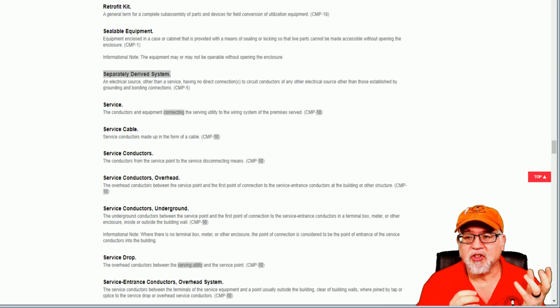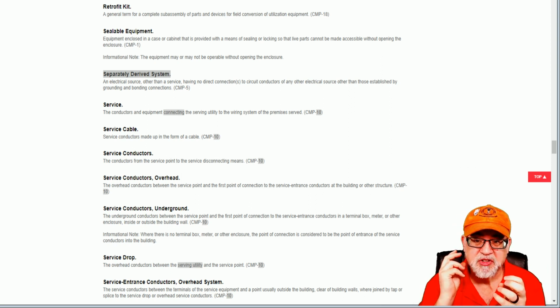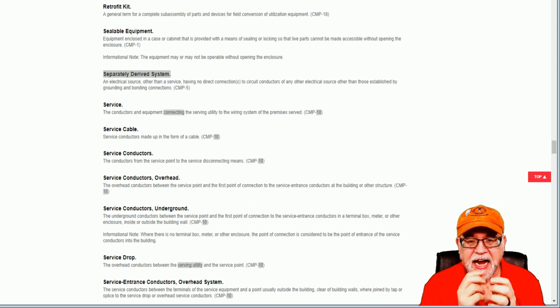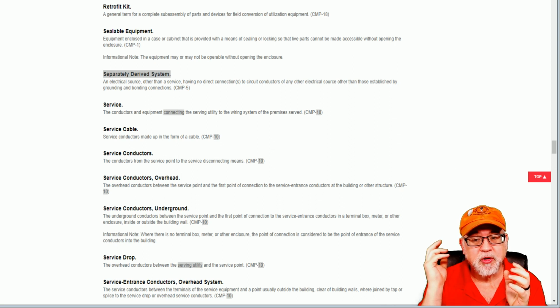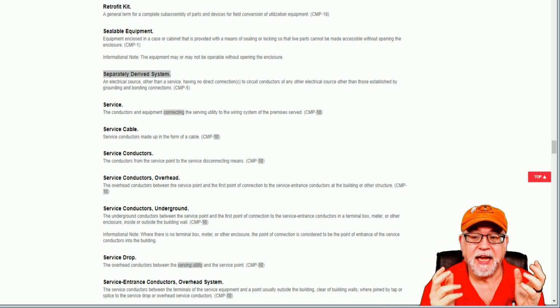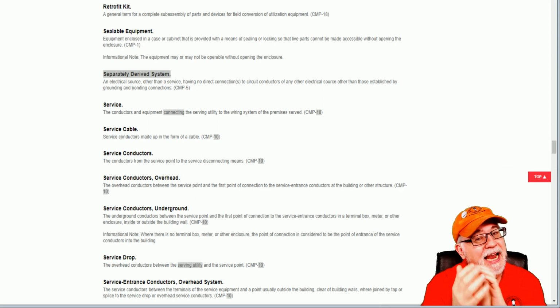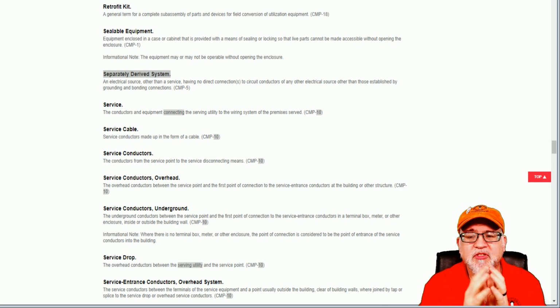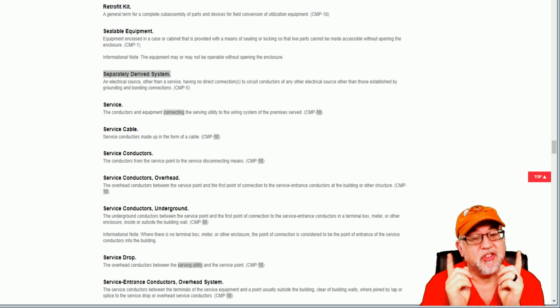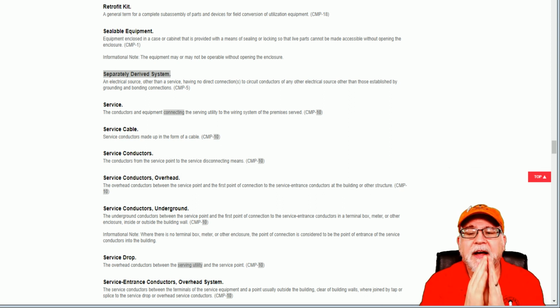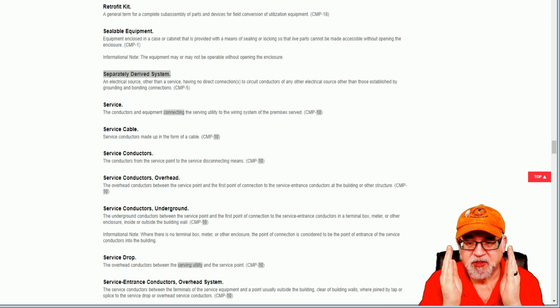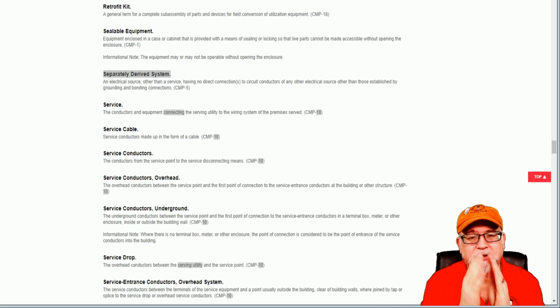So if I have conductors coming from the generator and I have conductors coming from the utility, and they're coming to a transfer switch, if I have a switching mechanism, and again, the result is it's all feeding a panel. So if the generator's running, the transfer switch is in a position that feeds that panel. But if the utility's running, it's in a position to feed that panel. Okay? So we're transferring between the generator and the utility. Now, if I'm switching all the ungrounded conductors, that's the hots, and I'm also switching the grounded conductor, generally a neutral, not always, but generally a neutral. If I'm switching all of them, then I have a separately derived system. It's two separate systems that are separated. They cannot come in direct contact.